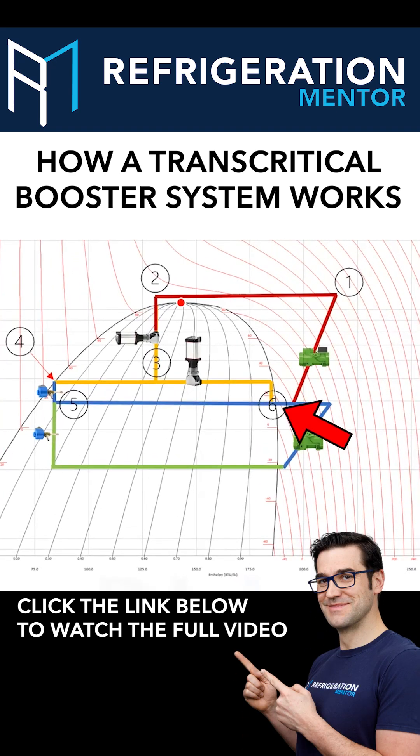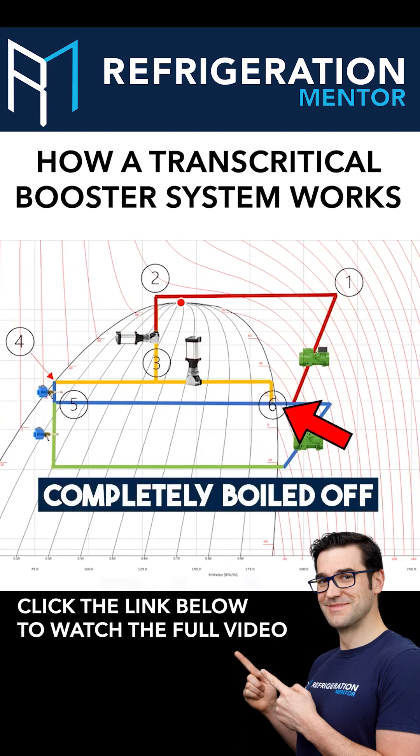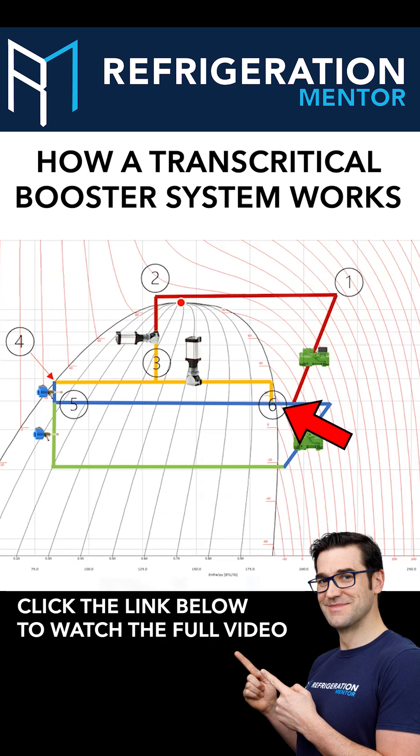Six, this is where the refrigerant has to be completely boiled off. You're hitting your dew point line and totally boiling off, so we know those medium temp transcritical compressors are not getting any liquid back to them.